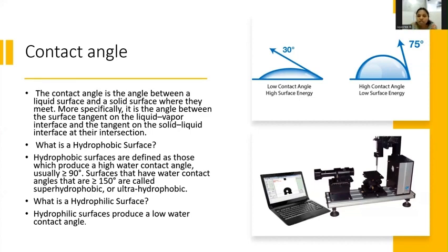You have to check whether the surface coating increases or decreases the contact angle. This is very important, because if the contact angle is very high, your cells are not going to adhere to your sample. It is just going to be away from your sample. Only if the contact angle of your implant is low, the osteointegration is going to happen. Otherwise, there is not going to be any osteointegration at all.